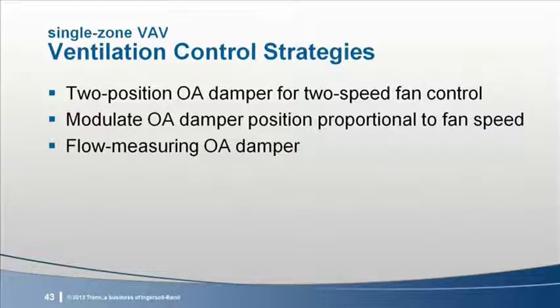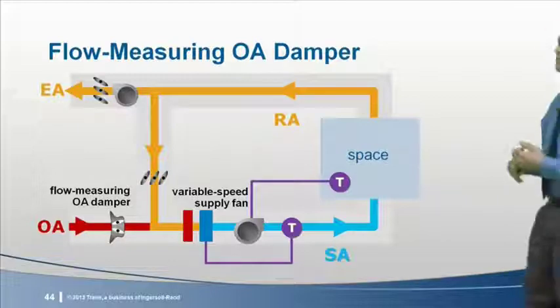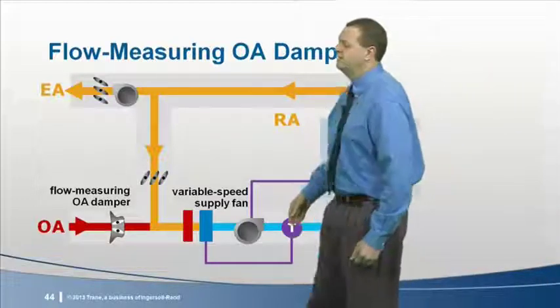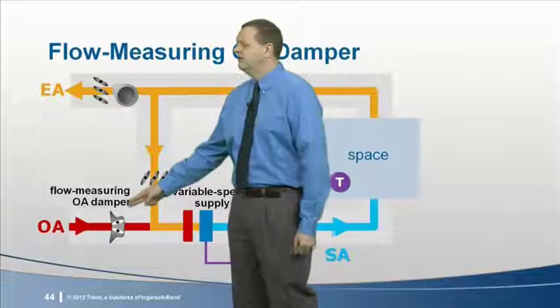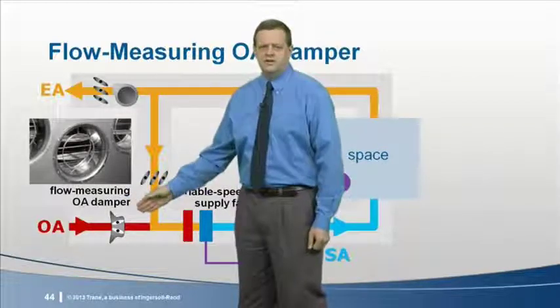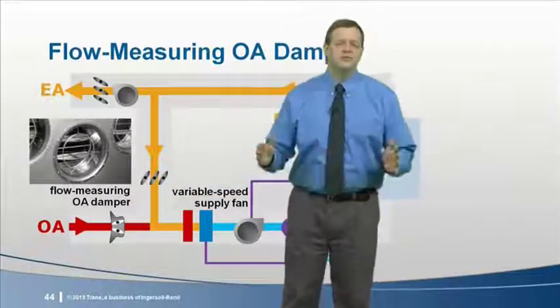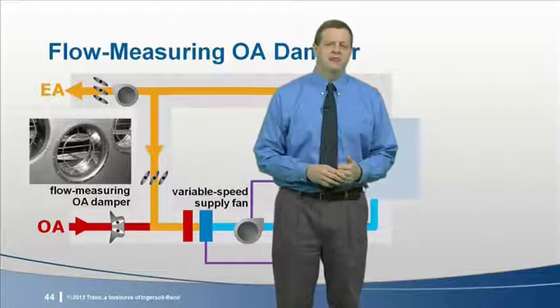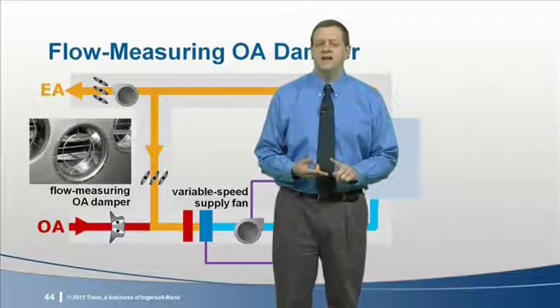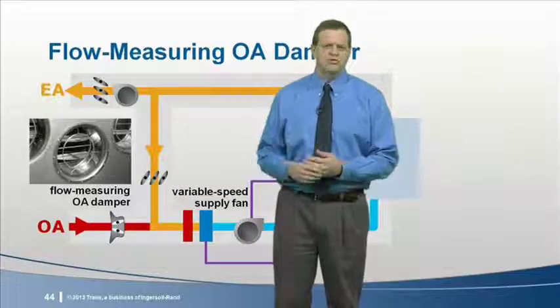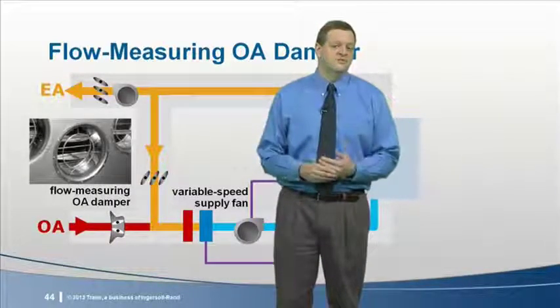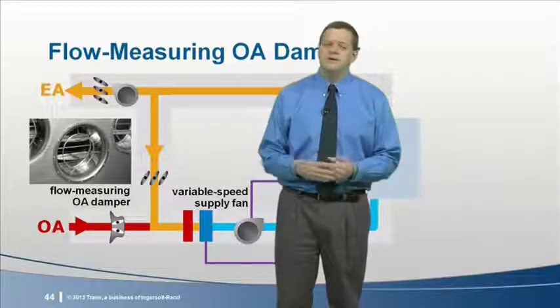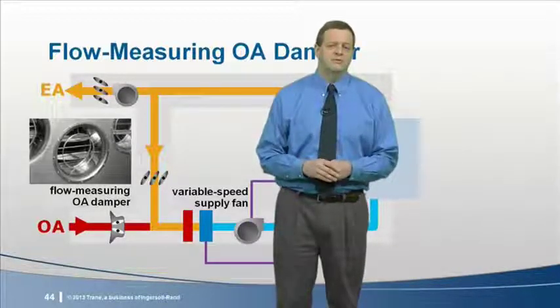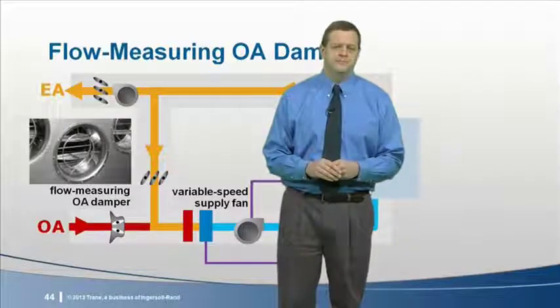Another method for controlling ventilation could be to actually measure the outdoor airflow and control it directly. This is typically accomplished by using a flow measuring device in the outdoor airstream, such as an airflow measurement station or a flow measuring damper. This method is more accurate over the range of airflows and can respond to pressure fluctuations caused by wind or stack effect. This direct control reduces the energy use associated with overventilation and has the added benefit of providing a means to document the outdoor airflow brought into the system over time.